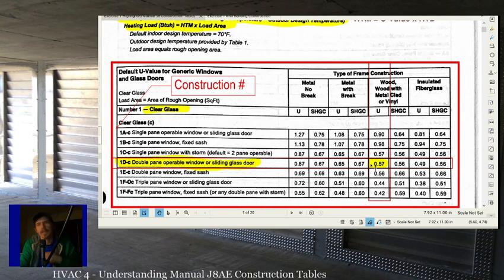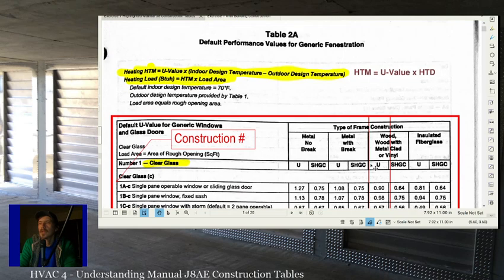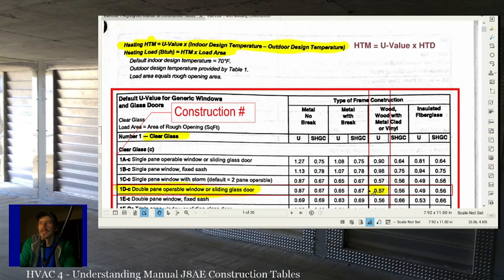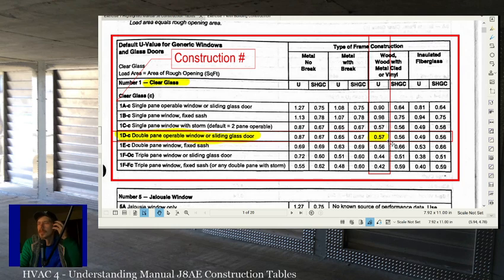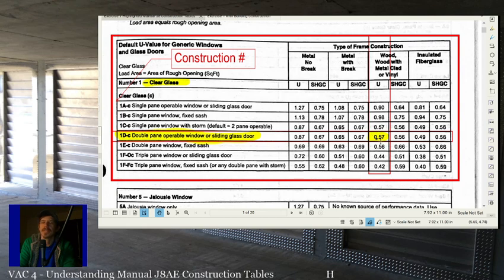So what you're going to find is that when we're doing heating, a lot of times we have to calculate our HTMs. With cooling, a lot of times we're going to already have the HTMs. Now Manual J8 is a little different than J7 on this. If you've ever looked at J7, it was slightly simpler on cooling than even this, but heating has always been like this for 30 or 40 years. With heating, the nice thing about calculating heating loads is we disregard any solar gains because their effect only helps us in the winter. And because the days are so much shorter in the winter, even though it only helps us, it doesn't help us a lot. So we can actually get exact, basically, BTU values lost.